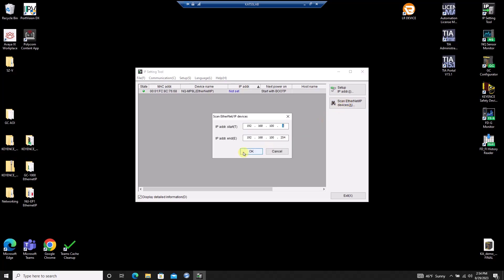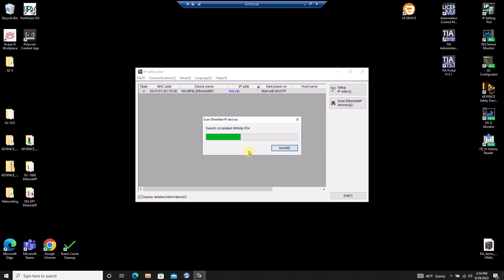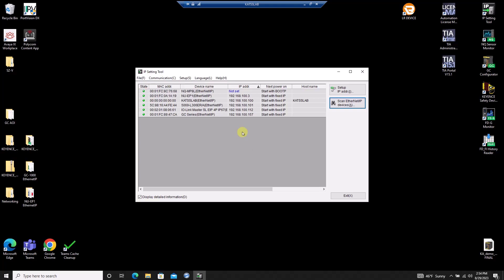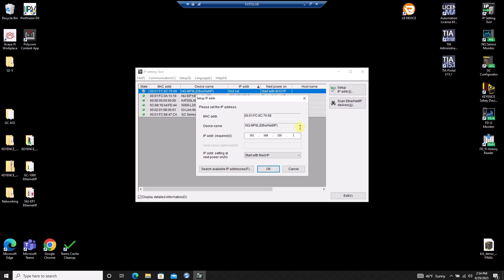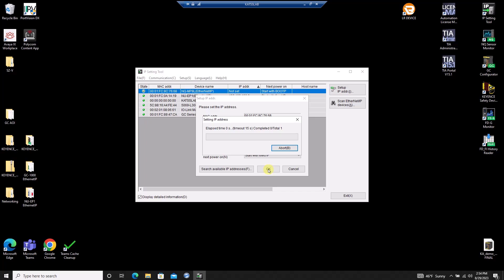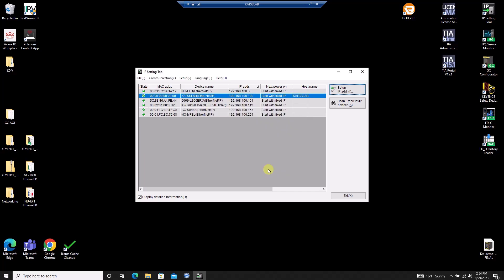From this screen, I can also search for any devices connected to the same subnetwork as my computer's Ethernet adapter. To establish an IP address on the NQ module, I want to make sure I have the correct row selected and select Setup IP Address. I'll enter the address I'm going to use and make sure Start with Fixed IP is selected so I don't lose the IP address after I power off the NQ. Once finished, I can confirm the IP address was successfully established on the NQ in the main screen.